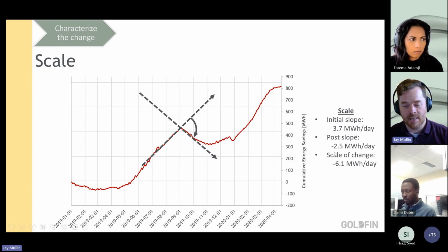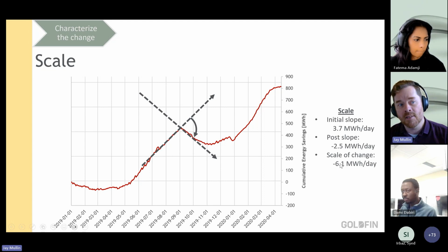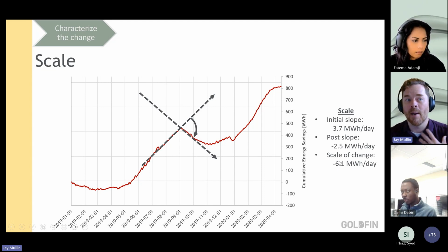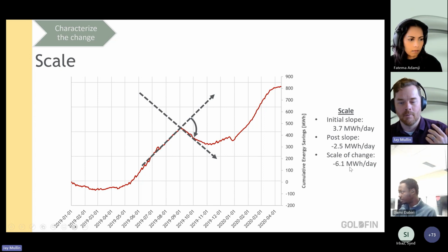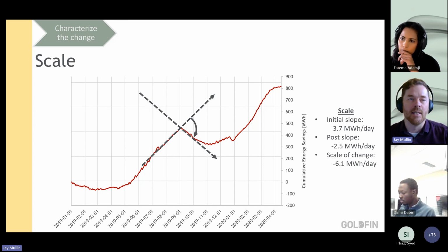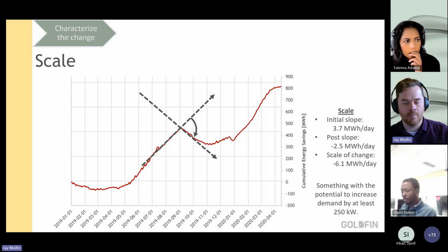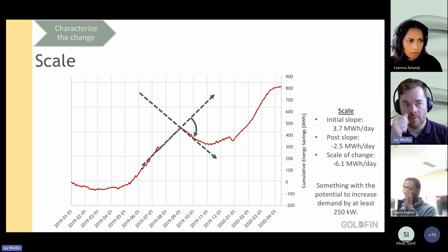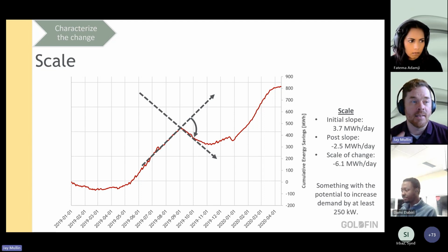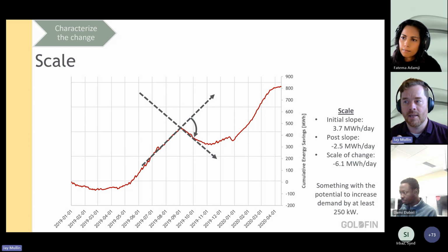After the change, we were having negative savings of minus 2.5 megawatt hours a day. So this change actually increased our energy consumption by about 6 megawatt hours a day. Now all of a sudden we have some sense of what might have contributed to this, like what equipment could consume 6 megawatt hours a day within our facilities. And if you divide that by 24 hours, you're looking at something with the potential to increase demand by at least 250 kilowatts. Again, this is all about trying to pick out more clues to help us get to where we want to be in finding the cause of this.